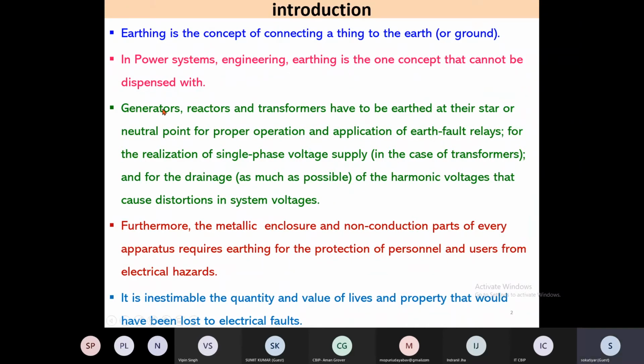The generators, the reactors and transformers have to be earthed at their star or neutral point for proper operation and application of the earth fault relays. Now, generators, reactors and transformers have star connected windings. The neutral point of the star connected winding has to be connected to the ground so that in the event any earth fault takes place, the current flows through the neutral, and there are a current transformer and the protection relay which will scan this current and disconnect the equipment.